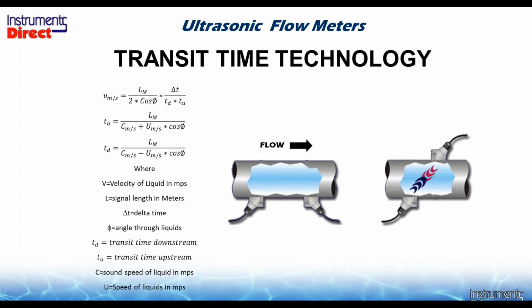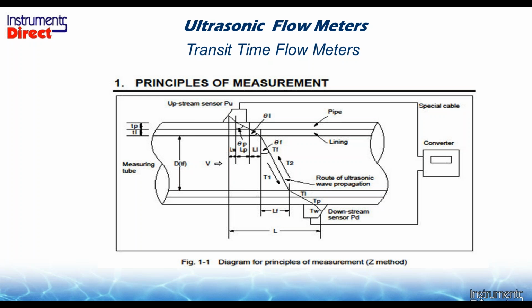Long ago, you had that giant big black suitcase that you had to open up and put these two huge pinging transducers on the outside of a pipe. Well, those days are pretty much gone. Back in those times, you could only use the basics of this equation, and if the sensors weren't aligned properly, or you didn't put in the right sound speed, the right material, the right temperature, then the two sensors wouldn't communicate to each other, and you had to futz around with it to get it to work. Today, there are many value-added features and autopilot functions in this device to compensate for those old technologies. So in most cases, the ultrasonic transit time flow meter, and especially the Fuji transit time flow meter, is very easy to use and very user-friendly to operate.